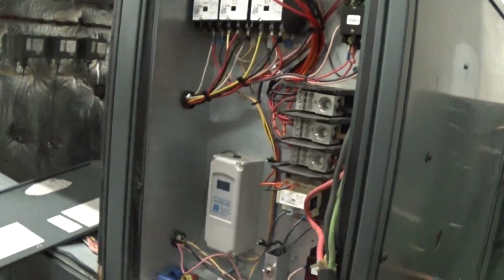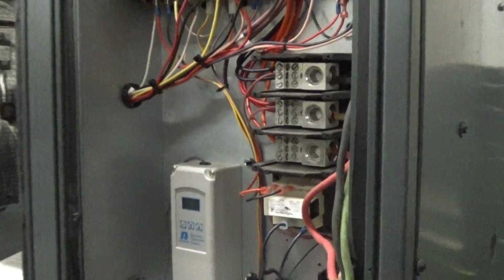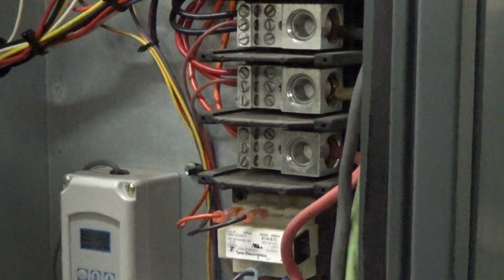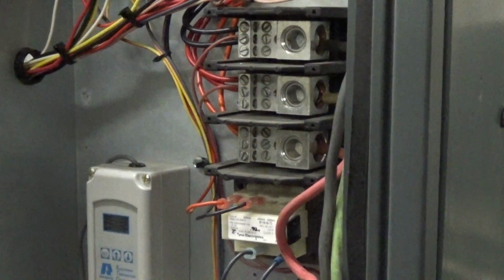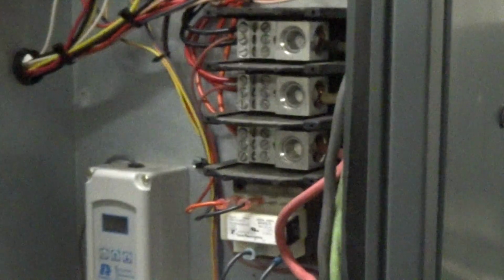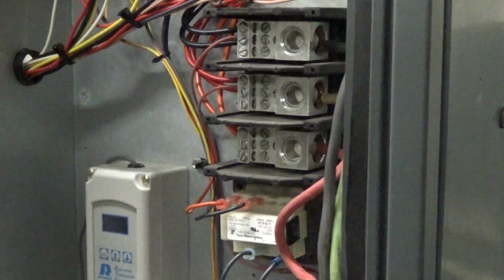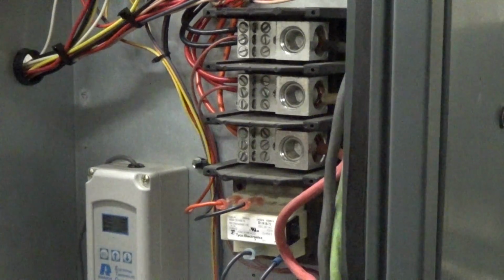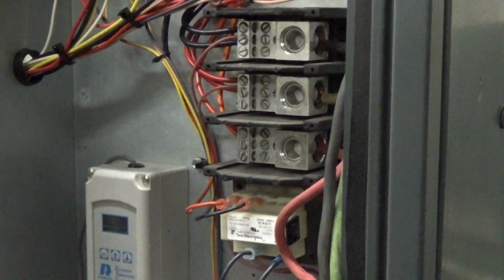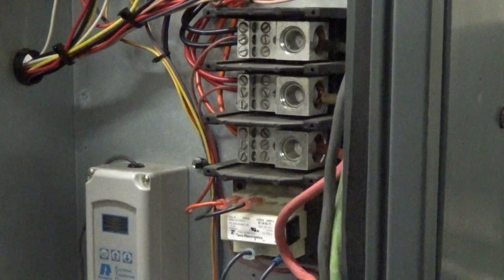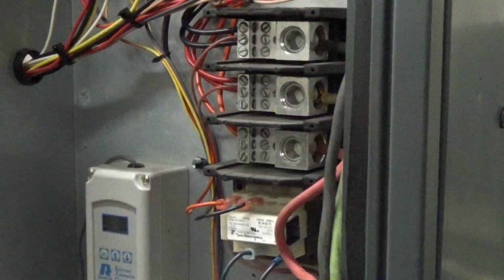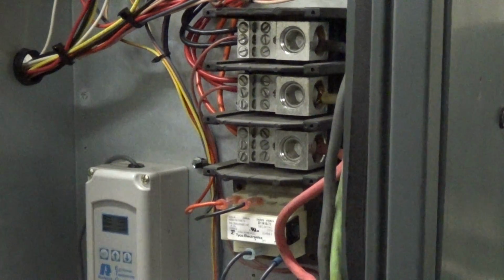Just to show you exactly what we mean for this particular customer. Now, our shop electricity, our low voltage, is actually about 204 volts. That's a little bit low, but it runs fine on that. Anything from 200 to just below 240, the unit should run just fine on. I'm going to take my meter here.